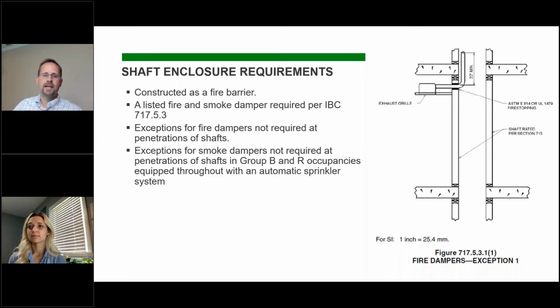So you're going to have a fan at the top of the shaft, and it requires it to be above all other connections. So it cannot be at the top level and then have another connection above it. It has to literally be above all the connections. And it says continuous upward flow. So that term continuous leads to the discussion of, does that mean that fan has to be on emergency power if you're using this exception?